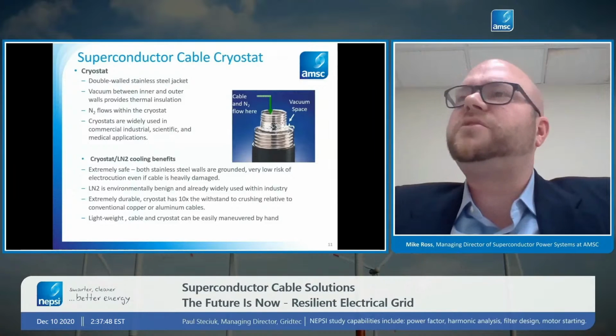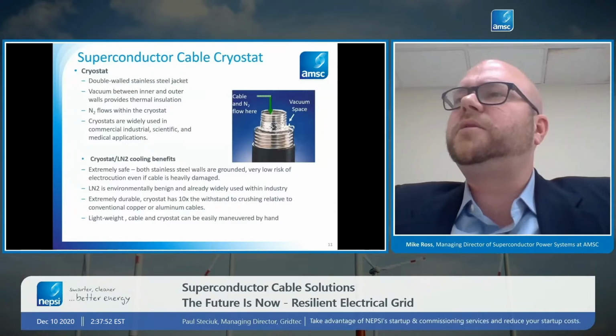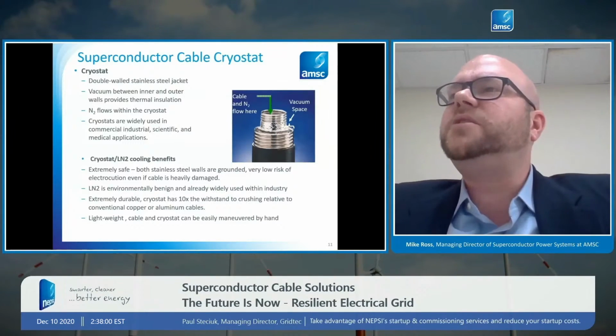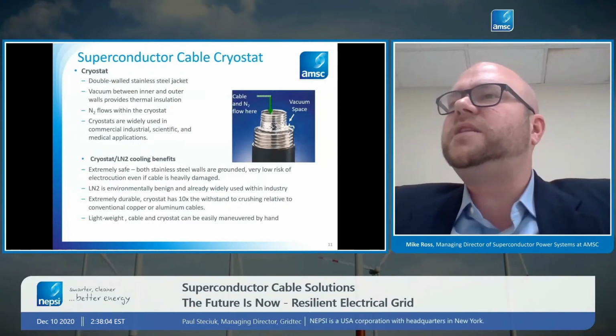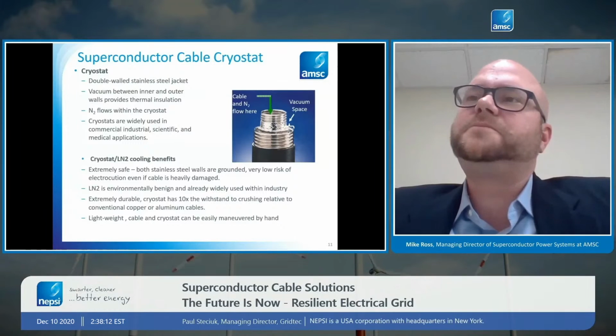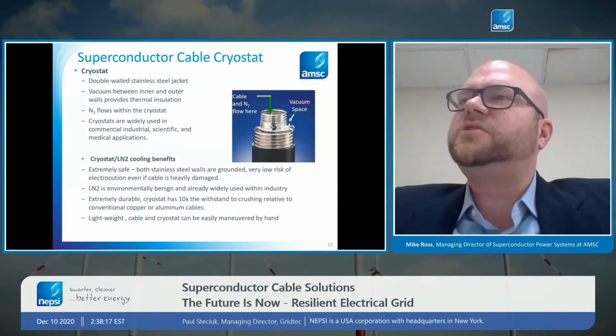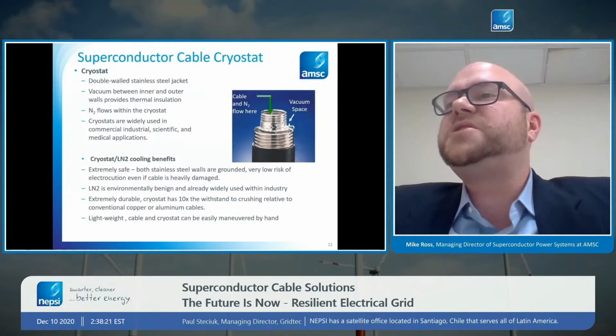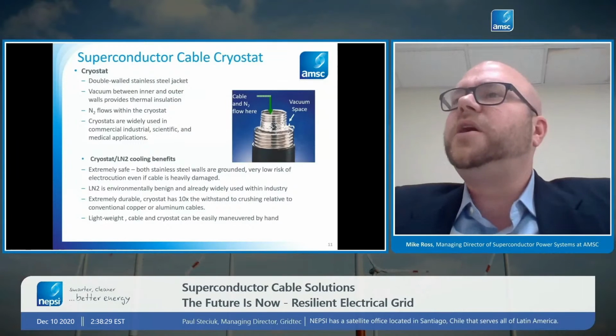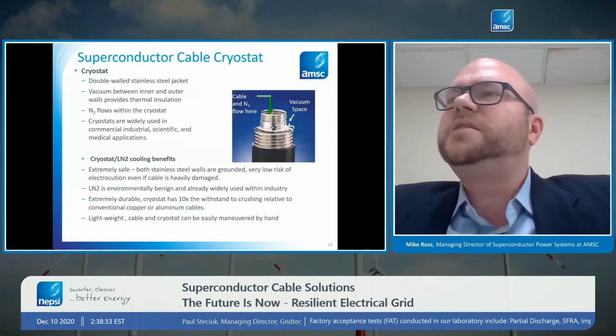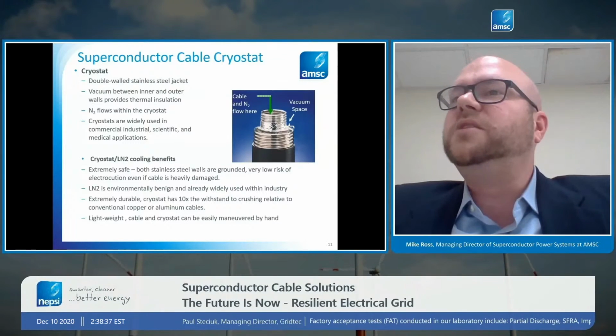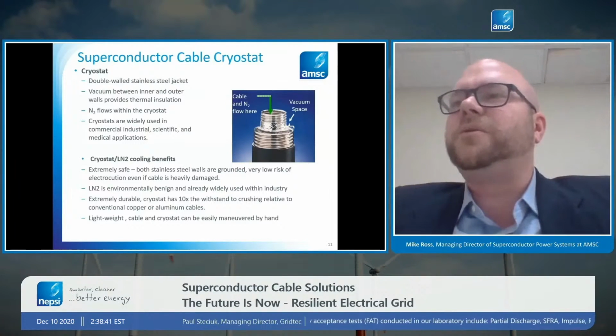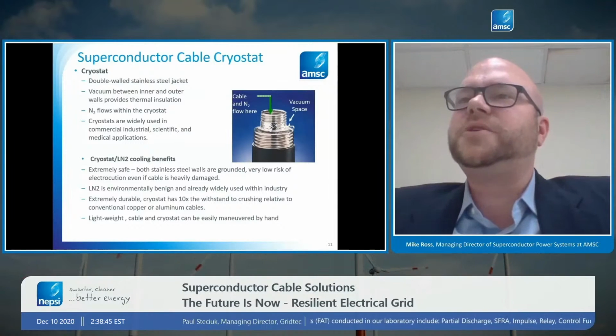They're very tough. They're made of stainless steel and so on. So you have a sidewall pressure strength or a crushing strength that's about 10 times stronger than the most commonly used utility cables today. And so what that means is that these cables can be pulled much harder. They can go around corners much better than conventional cables. Additionally, because there's all this stainless steel in these cryostats, you essentially have, from a safety perspective, a double-walled conduit. So in the event that someone dug into the cable, there was some kind of fault in the cable, you have all of this grounded metal around your power cable that the electricity can be grounded into, which makes it less likely that whoever is running the backhoe that dug up the cable or whatever will be injured by the electricity in the cable.